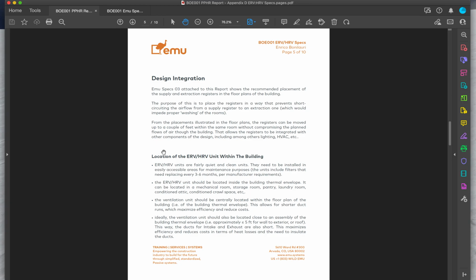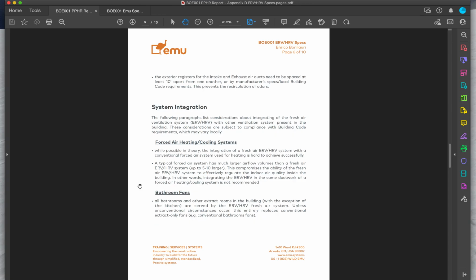Design integration, some recommendation as far as where to locate the unit, inside the envelope, something that is accessible. So read that. This is something that's going to be useful for the architect or designer of the building. Then integrating that with other system for their heating and cooling. That is something that is on paper possible, but in our experience it's very hard to do, so we typically recommend not trying.